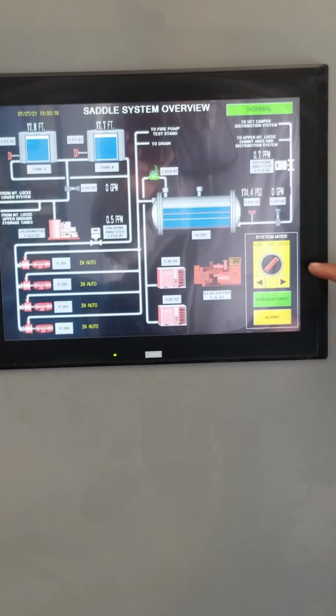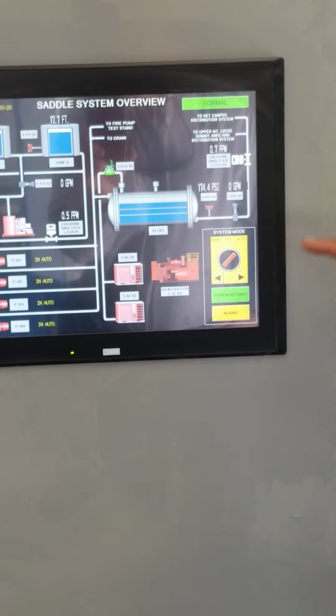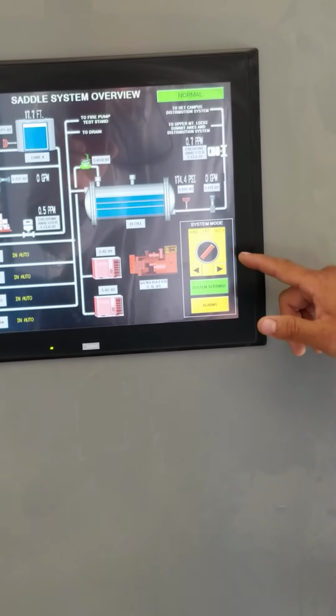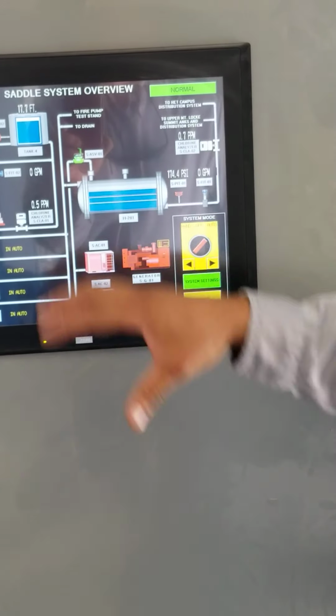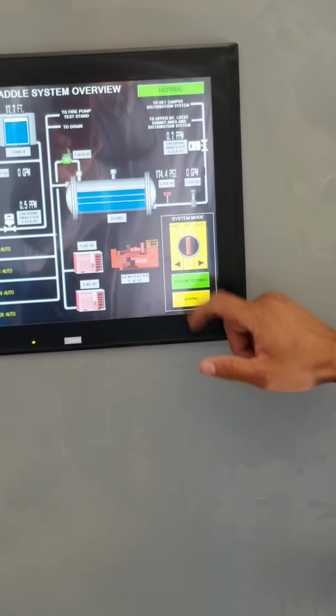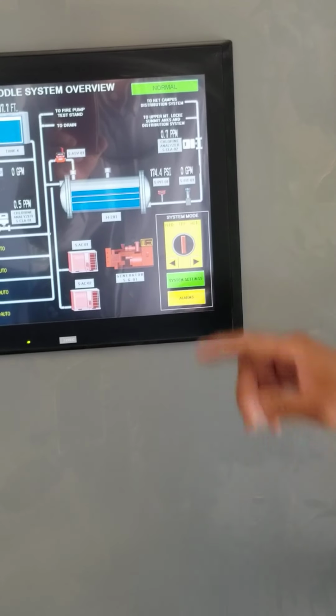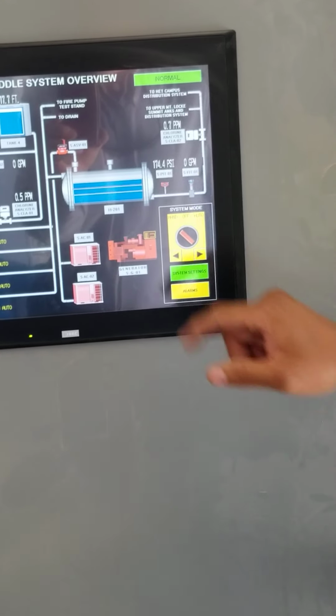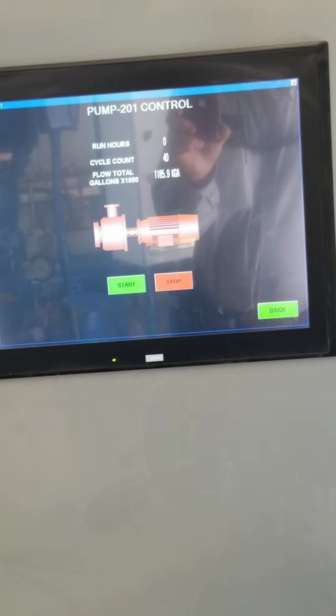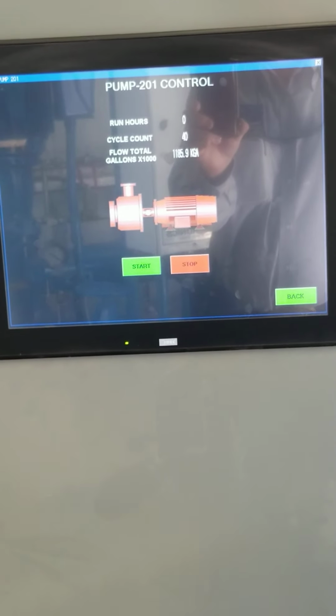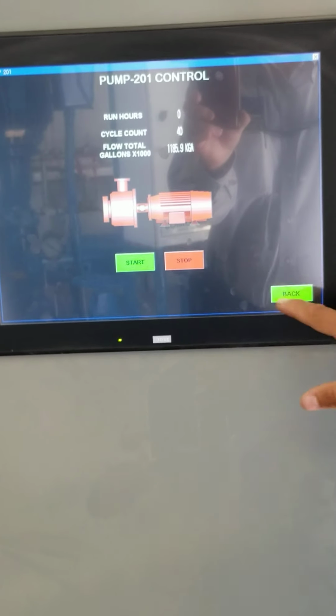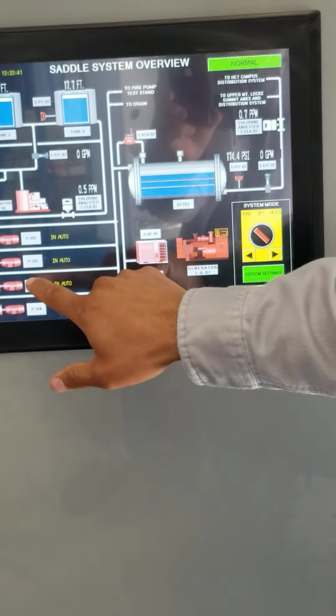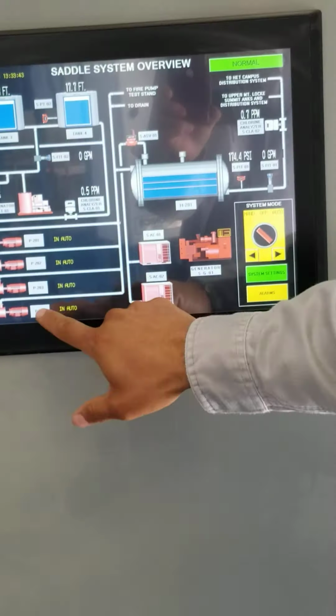This screen is very important. This is your main hand-off auto to operate the system. When you have it on automatic, the system will take over. When you have it on off, of course, nothing will work. When you have it on hand mode, you physically have to go to each and start it yourself. The operator will take over. The system will no longer take over. So you will go to each individual and start as many pumps as you want.